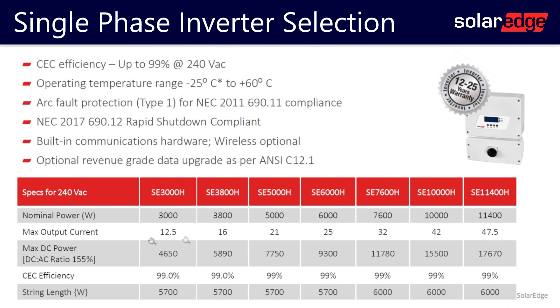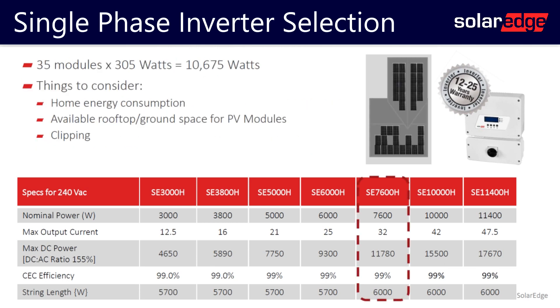SolarEdge single-phase inverters with HD-Wave technology allow a maximum DC to AC ratio of 155%. That means if I have a 10 kilowatt AC inverter, I can put 15.5 kilowatts DC on it. Our system size is 35 modules at 305 watts, yielding 10,675 watts. That means the smallest inverter I can use is a 7.6 kilowatt inverter.